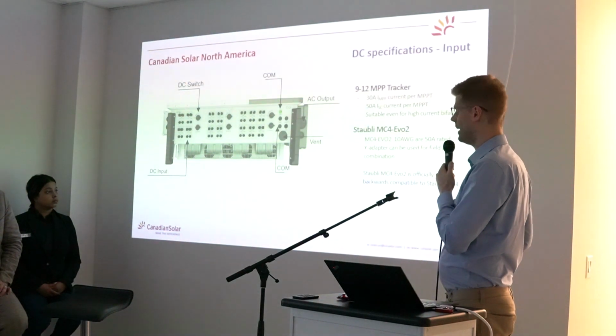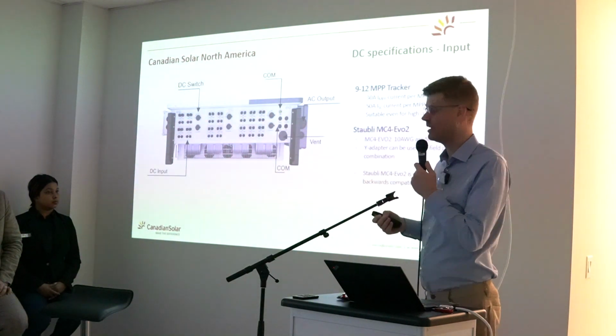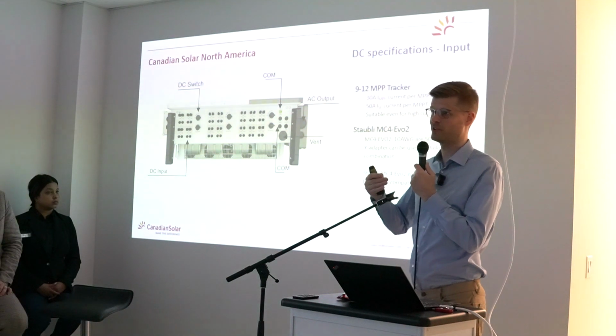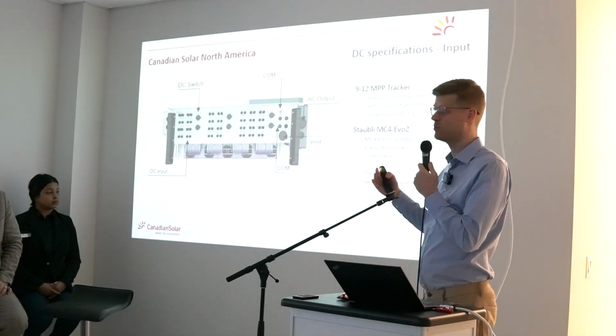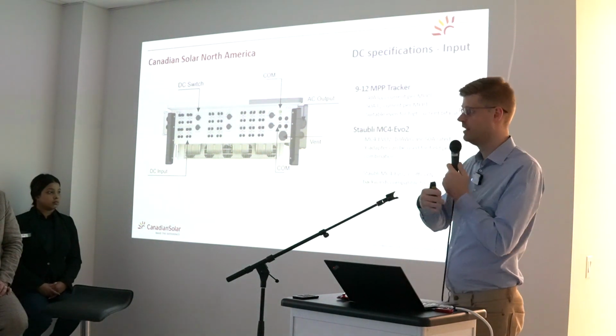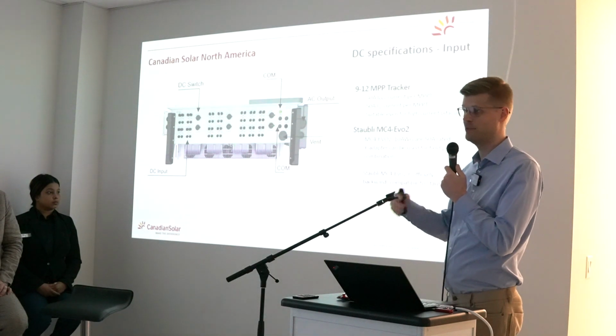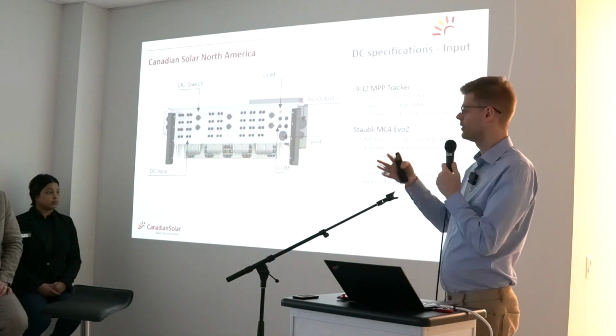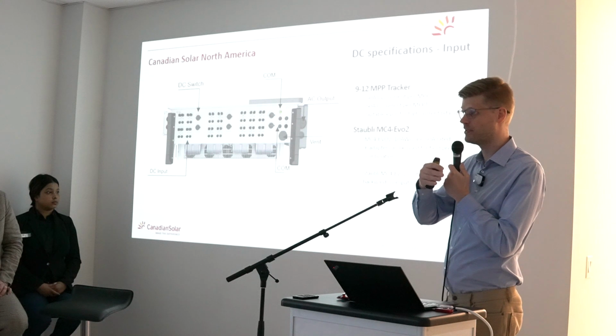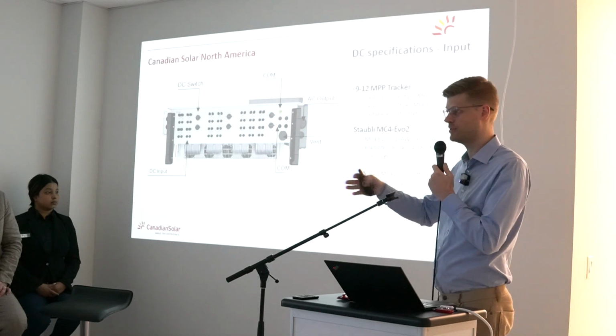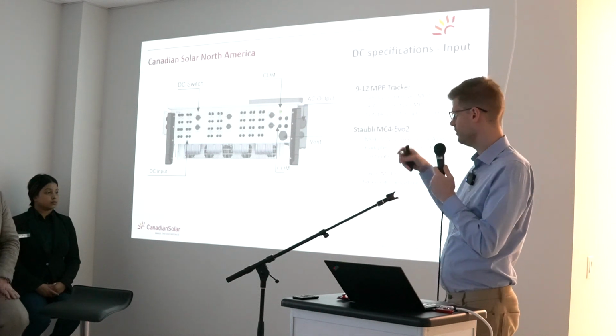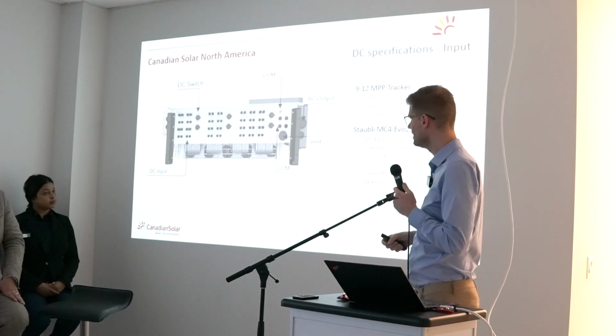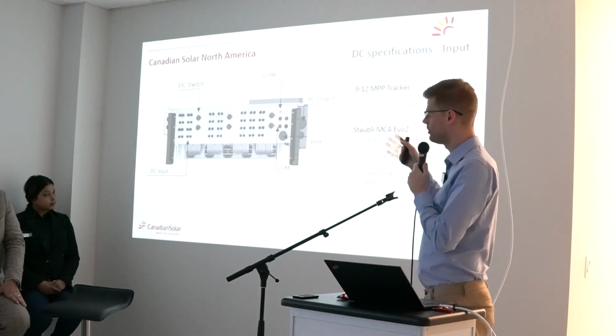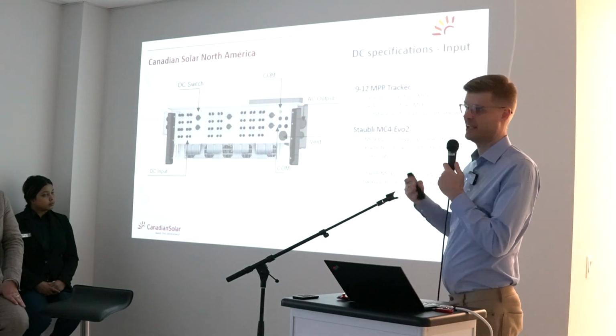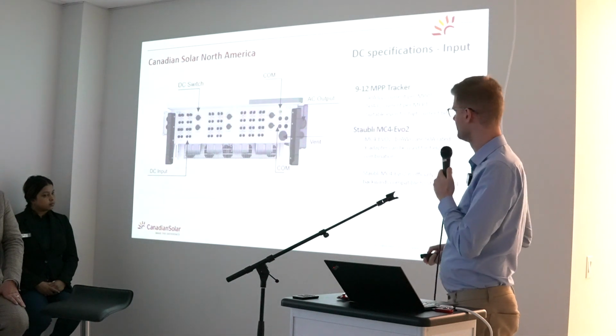You can also use a Y adapter in the field. That would be advantageous if the inverter is maybe a little bit further away or if you want to do some pre-combining in the field, that you have a ground mount racking system, you have 2 rows, for example. You can combine these rows in the field and then have only one conductor positive, one conductor negative, excuse me, to each input to just save cable and wiring in your system.